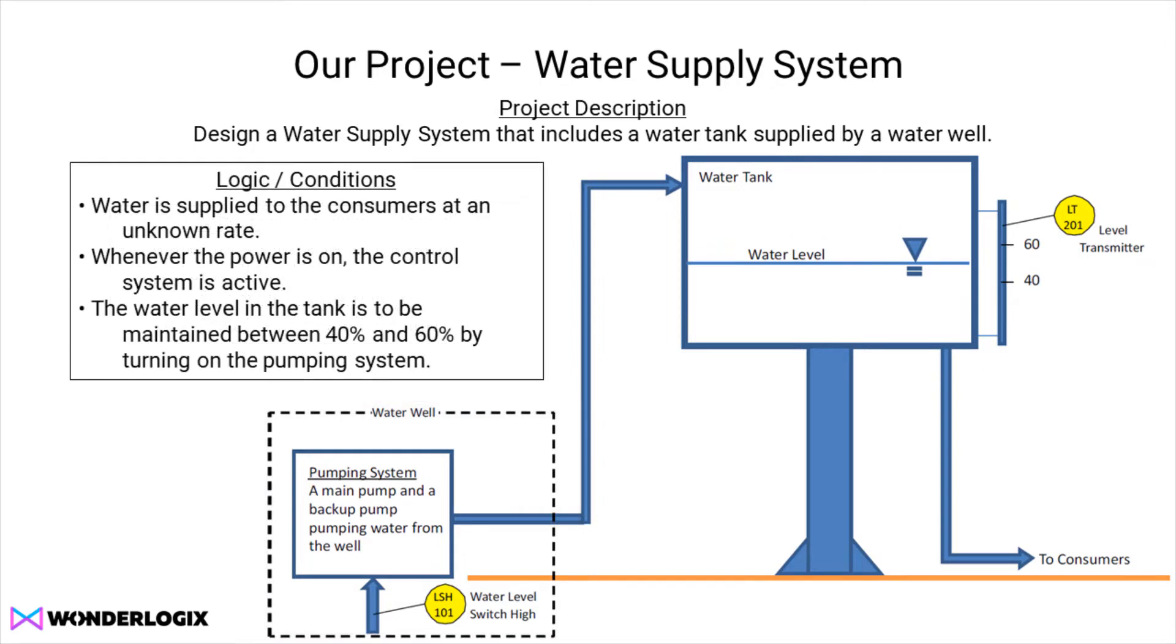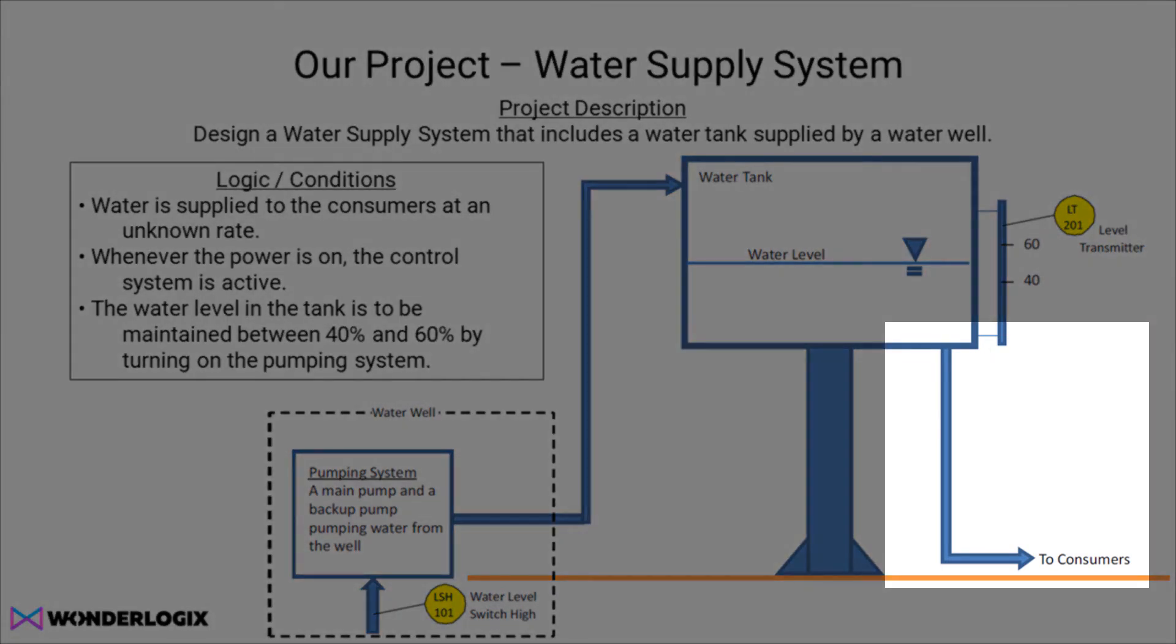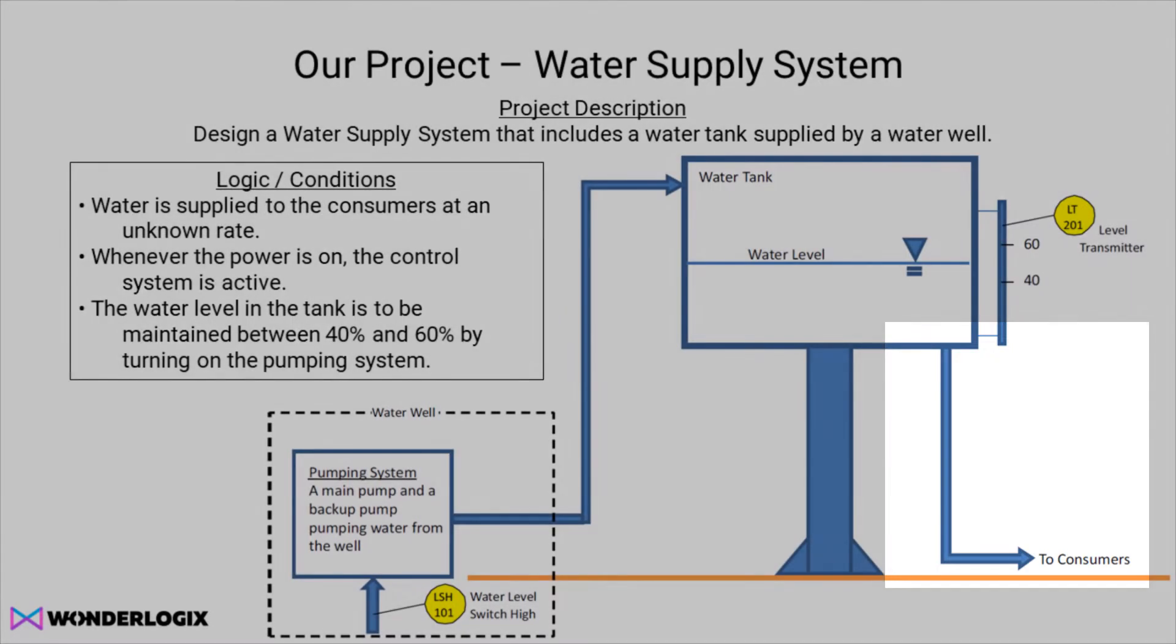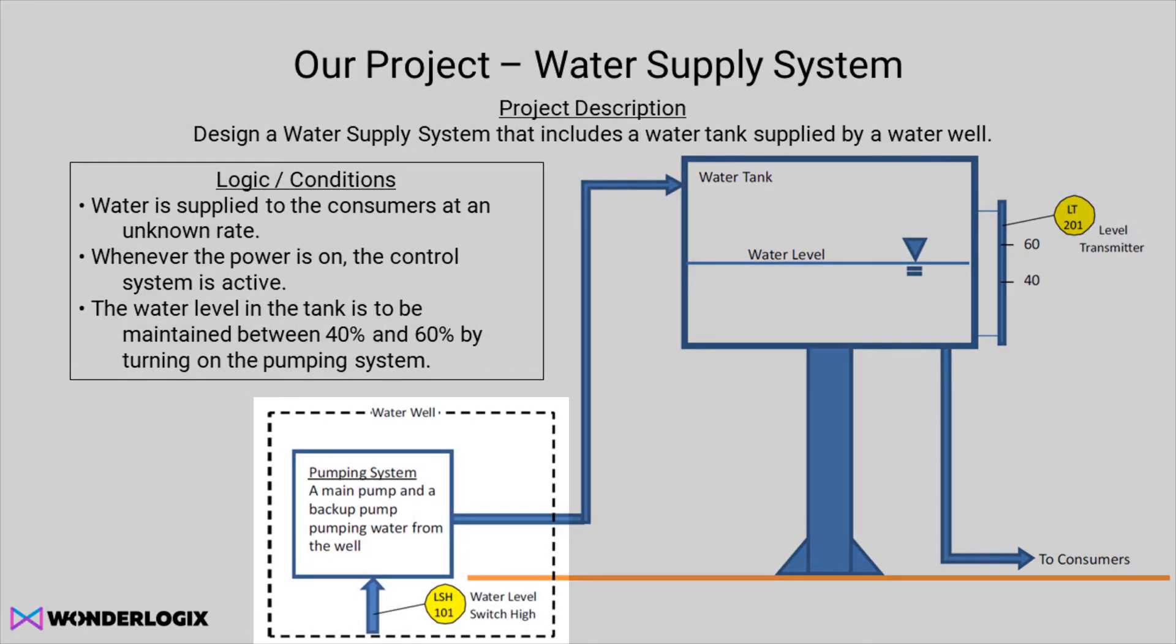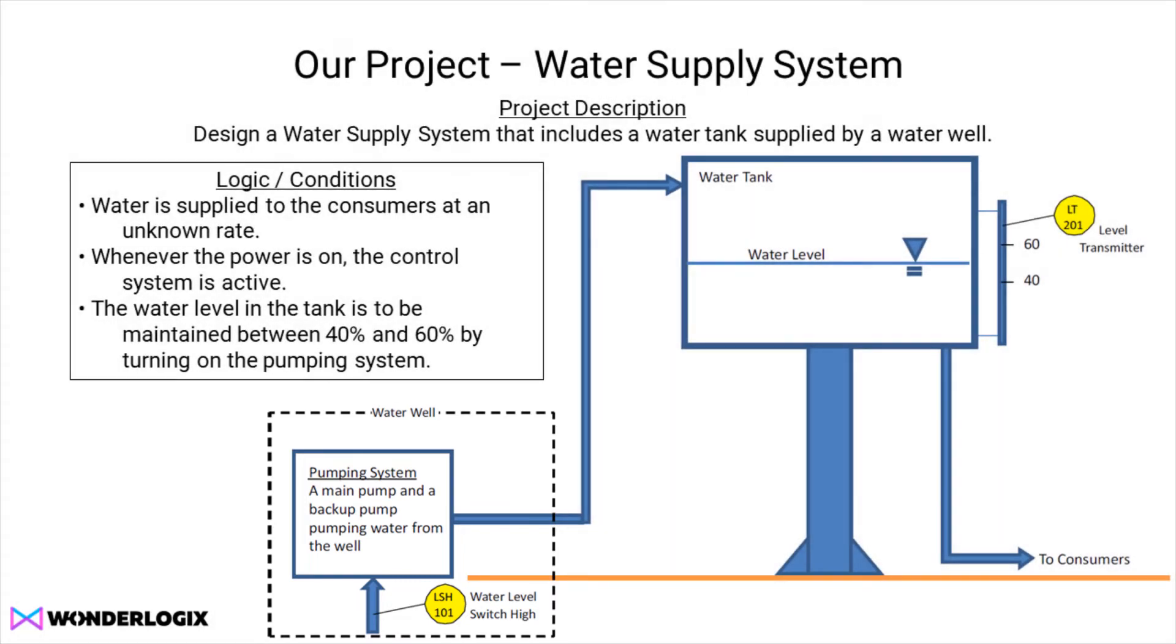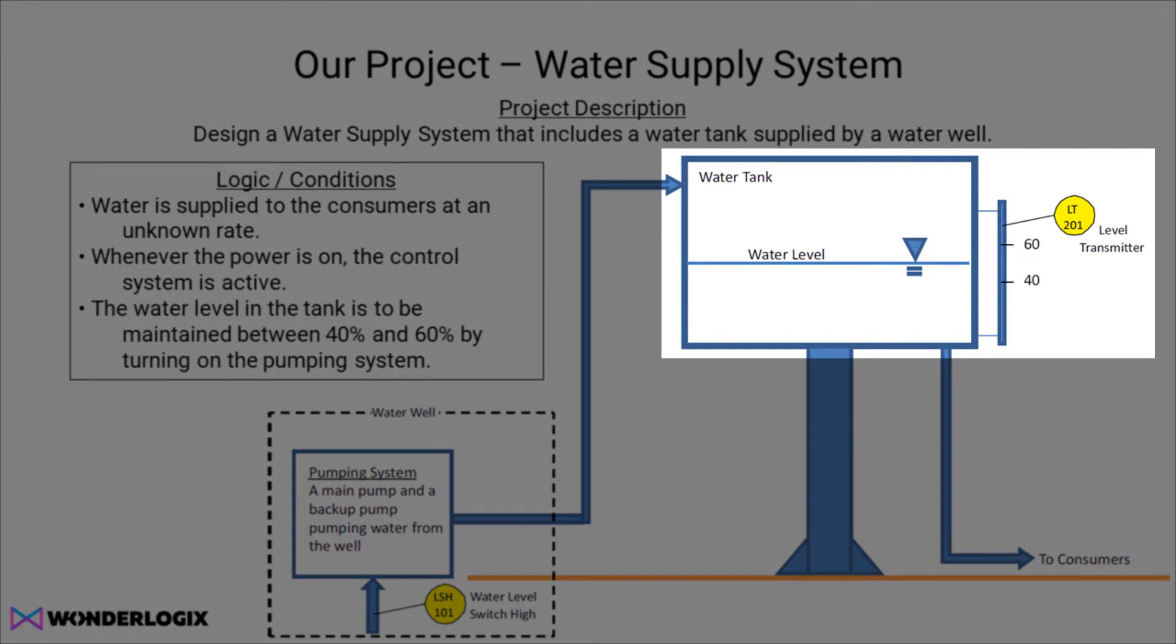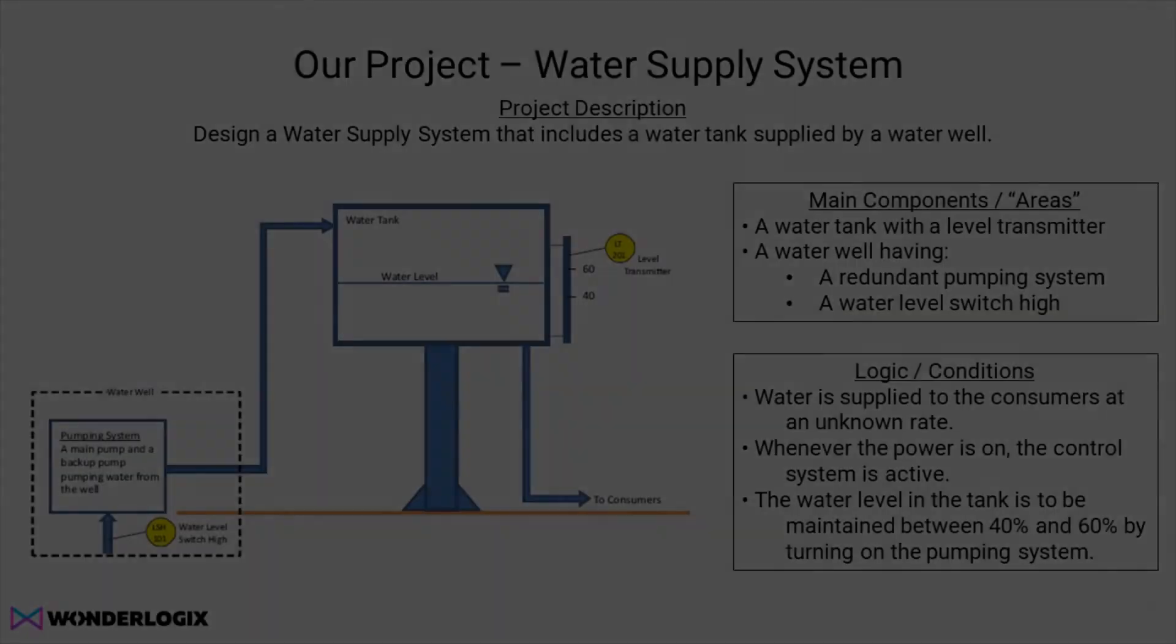Here are the conditions for the project. Water will be supplied to the consumers at an unknown rate. Whenever the power is on, we want the control system to be live so that it will pump as it needs to. We're trying to maintain the water level in the tank between 40 and 60 percent. If it drops below 40, we'll turn the pump on. If it gets up to 60, we'll turn the pump off.